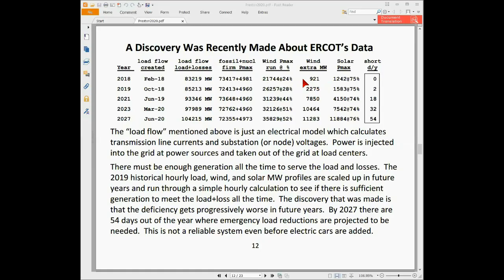They needed a little extra generation—by the way, they're running solar at about 75% in all these cases. There was 1,242 megawatts nameplate rating of solar in 2018. They needed a little extra power in the load flow case in order to solve it. They basically had all the fossil fuel plants and the nuclear plant running wide open, and since they didn't have quite enough generation, they pulled a little extra from the wind.